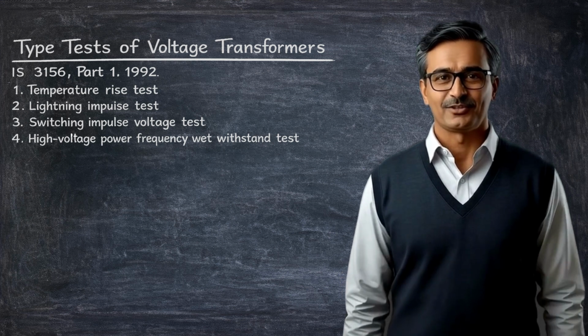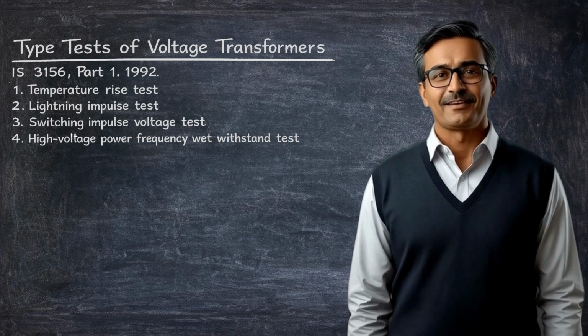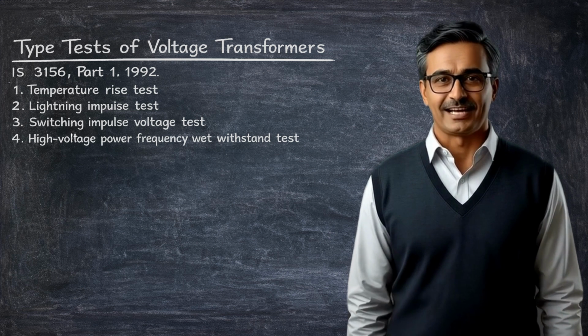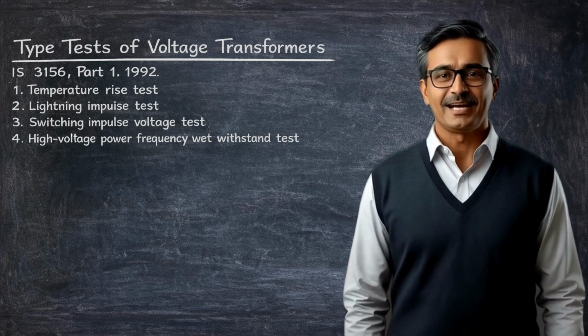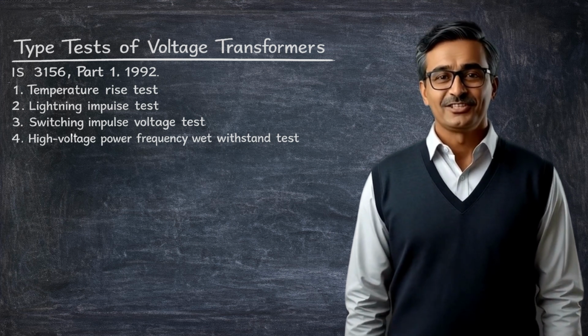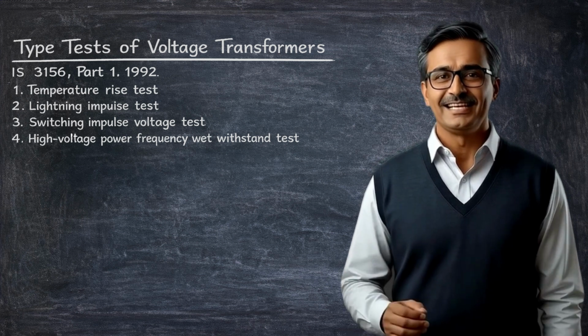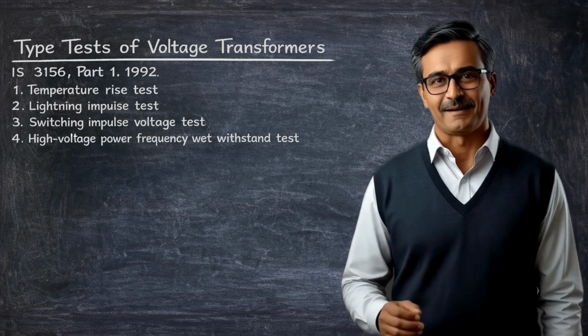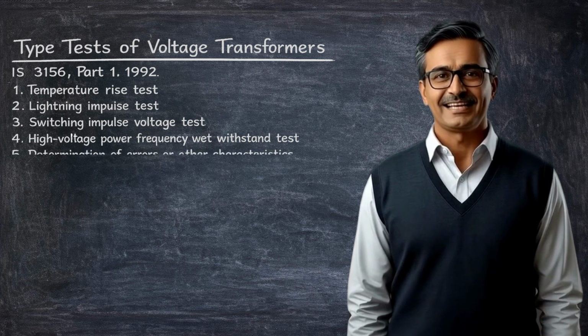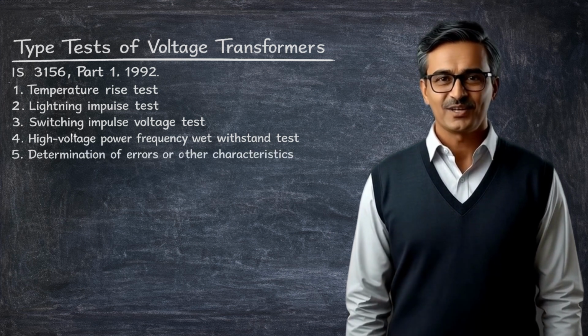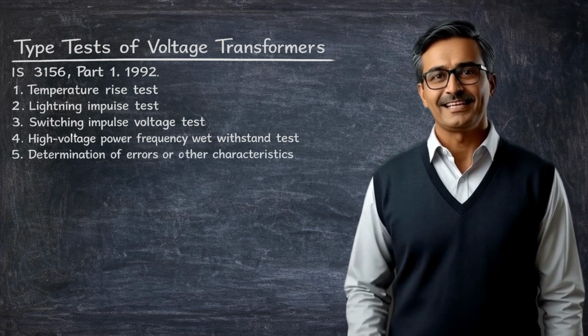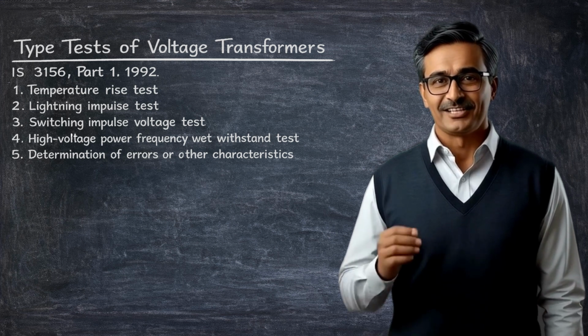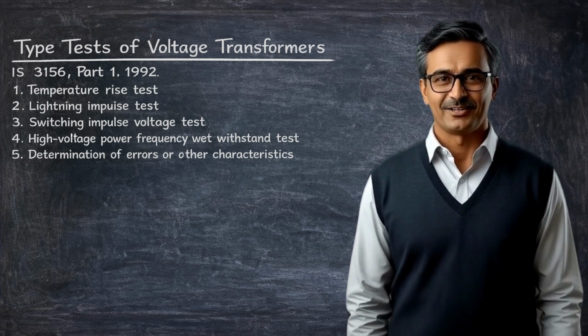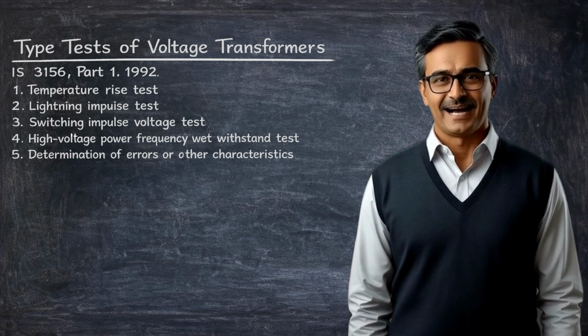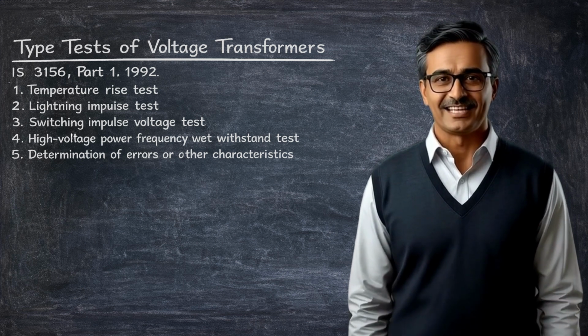There is an important note regarding this test. If the porcelain weather casing or bushing has already been tested separately under wet withstand conditions, then the requirements of this test are considered to be satisfied. The final type test is the determination of errors or other characteristics. In this test, we check whether the voltage transformer meets the required accuracy class or designation as specified in the relevant parts of the standard.